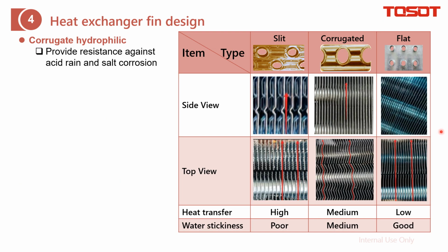Heat exchanger fin design. First, we go to the fin structure. Actually, in the factory design system, there are 3 kinds of fin, which are the flat, the corrugated, meaning the surface is not flat but goes up and down. The purpose of this one is to increase the air turbulence. And the next is the slit fin, where on the surface we cut lots of slits. The purpose is also to increase the turbulence when the air flows by. And as you know, the higher the turbulence, the higher the heat transfer efficiency we can get, right? So the side view and top view for these 3 structures are a little bit different, just for your reference.